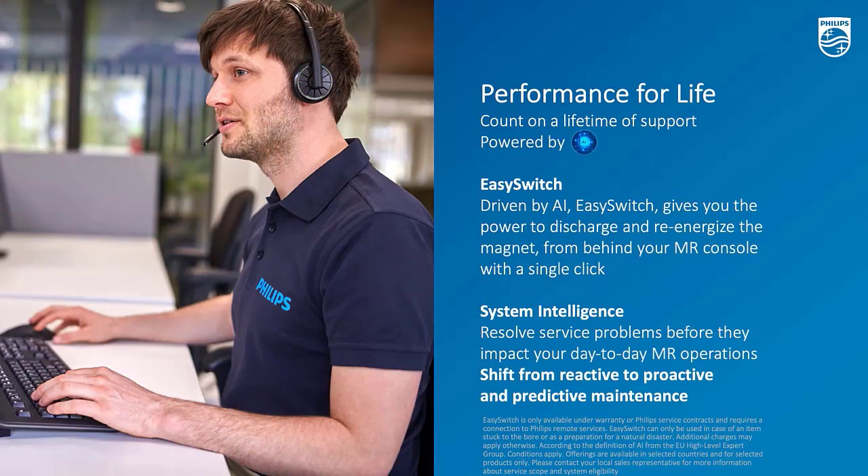The third one is Easy Switch functionality. This is unique and only applicable to helium-free MRs. Easy Switch allows you, in case of emergencies — such as a quench or an object stuck in the bore — to de-energize the magnet. Easy Switch is driven by AI algorithms, and thanks to the BlueSeal magnet, no helium will evaporate or be lost during the emergency. With this Easy Switch technology, you'll be able to re-energize the magnet easily from behind your console with a single click, and have your MR system up and running in about one to two days, compared to a conventional magnet that can take up to seven to ten days.